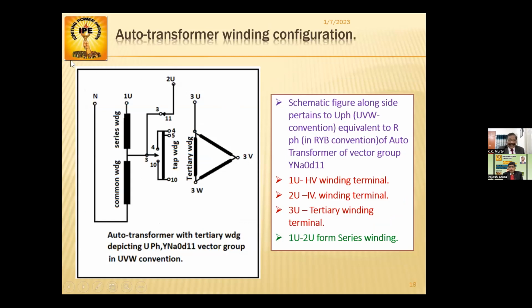One must understand what the series winding is, so for clarity I have given this slide. This is the basic schematic diagram of an auto transformer in UVW convention. Basically, when you see the transformer, you will not find RYB on the bushings. You will find UVW. U stands for R phase, V stands for Y phase, and W stands for B phase in RYB convention.